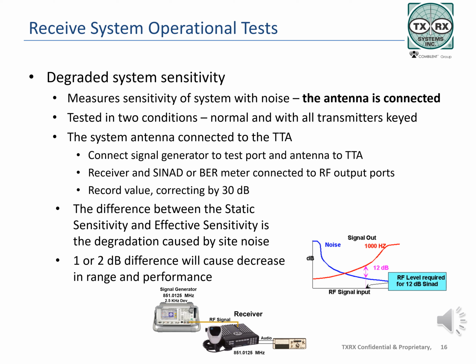This testing should be performed under two conditions, the first under normal operation and the second with all transmitters keyed and producing full power. Remember that all transmitters produce noise when they amplify signals. When all of the radios in a system are being used, the system is fully loaded, simulating an emergency situation with all radios in use, and when system failure or compromise cannot be tolerated. This will also be the time when the system has the potential to generate the most noise.